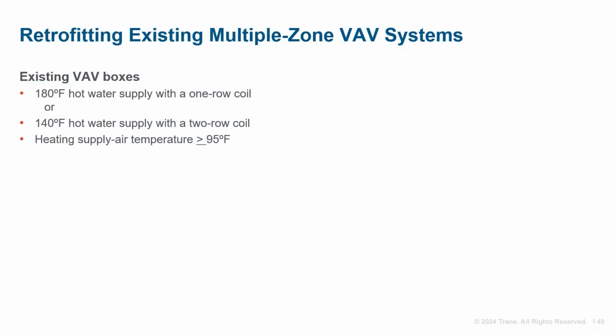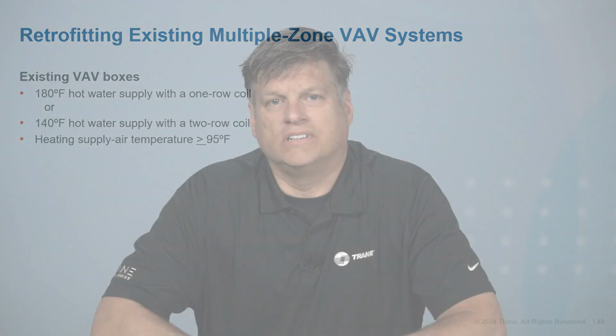Let's look at retrofitting another common system type, the multiple zone VAV system. When retrofitting this type of system, the existing VAV boxes usually contain either an electric heater or hydronic coil with a hot water supply of 180 degrees or 140 degrees. These systems commonly have a heating supply air temperature of 95 degrees or higher. Today's heating design standards prescribe a lower supply air temperature when heating to reduce energy use. This is unrelated to heat pumps.